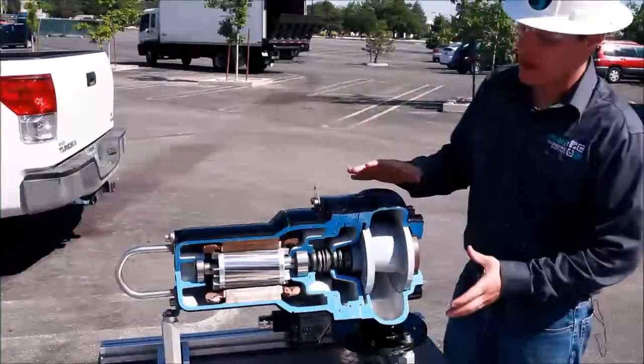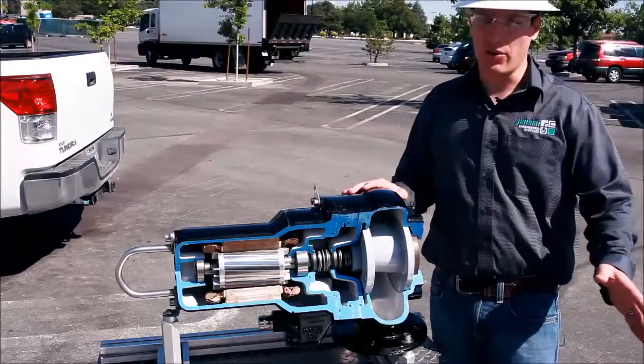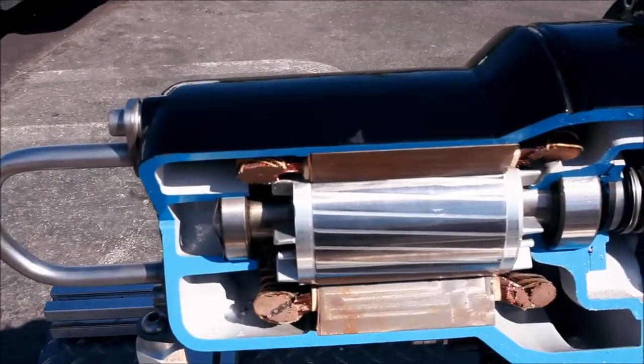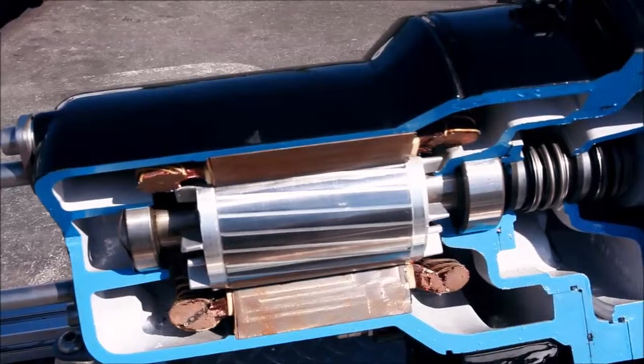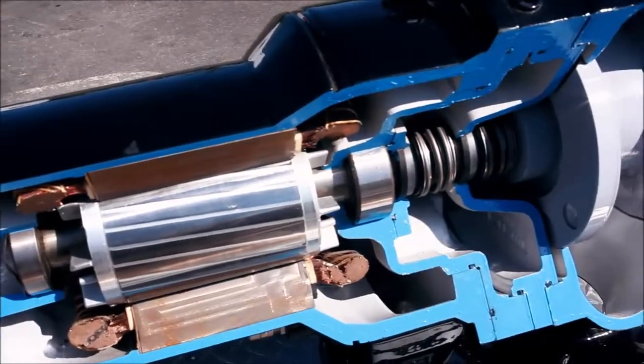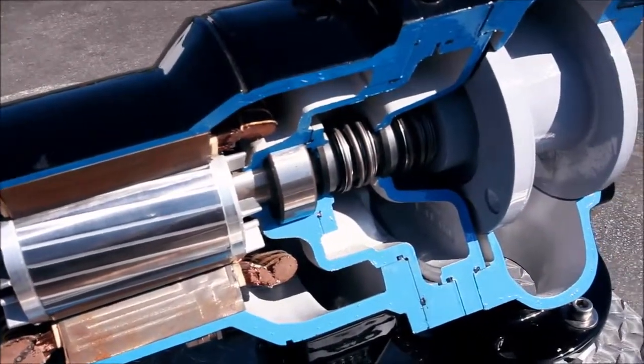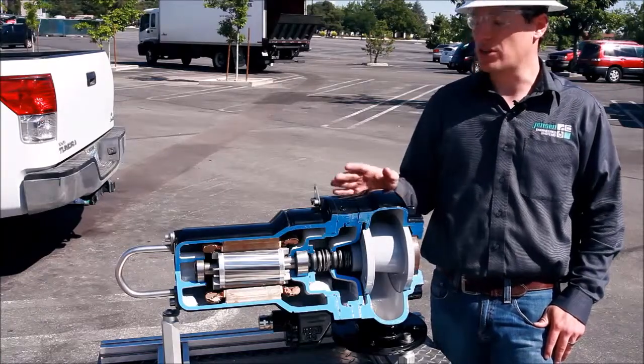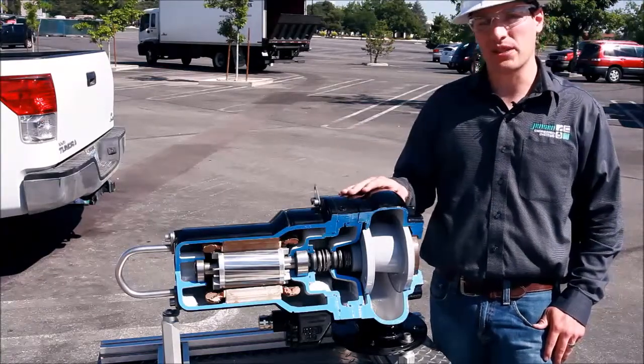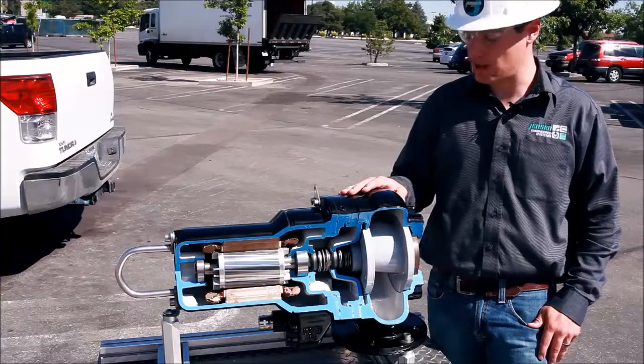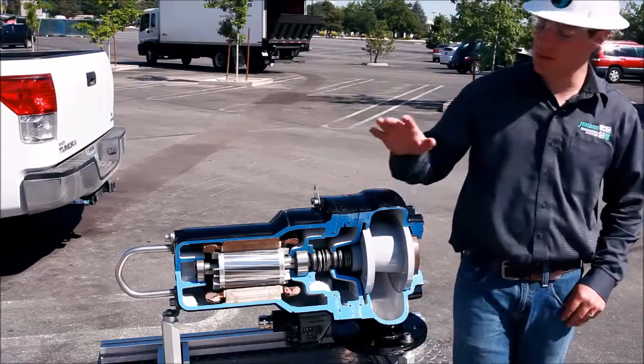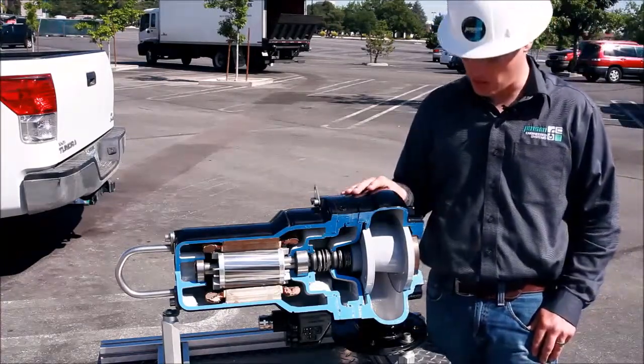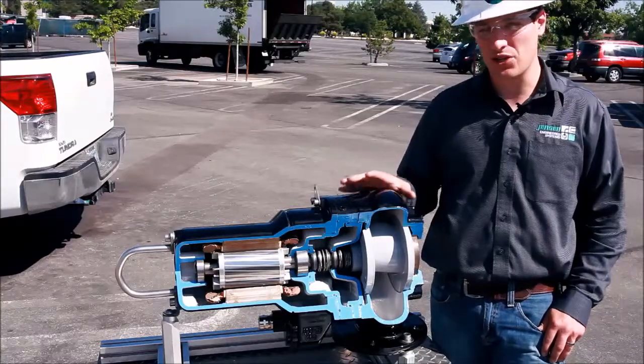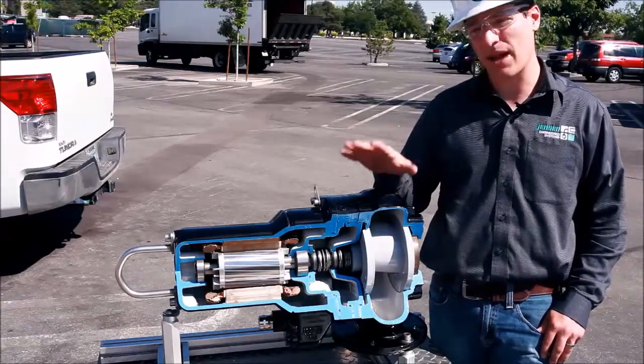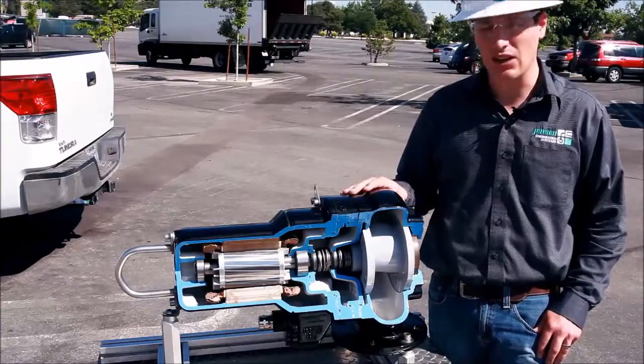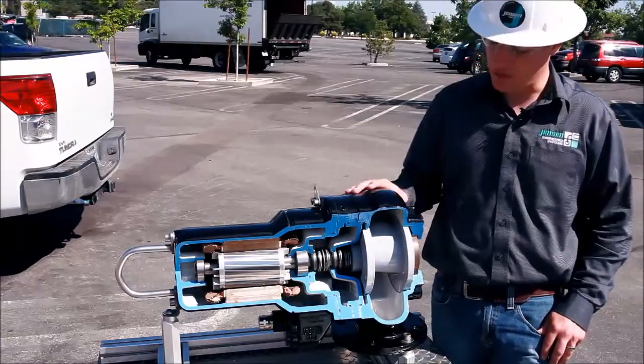All right, so here is a cutaway version of the same exact pump that's in the wet well. This is, again, an AMX 434 as manufactured by Homa Pumps. Homa Pumps is based out of Connecticut, and Jensen Precast is an original equipment manufacturer that utilizes Homa Pumps in our submersible pump stations, packaged pump stations. Some specifics about the pump we want to make you aware of: this pump is capable of passing a 3-inch solid, so it's not going to clog with any solid up to the diameter of 3 inches.